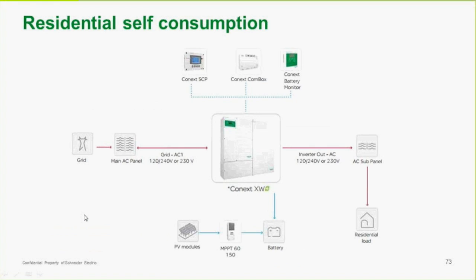Residential self-consumption. So now we're tied to the grid. We have our main panel again. But in this case, we have the PV modules and a charger, and those are actually charging the battery, and that excess power is being supplied through the inverter to the loads that are hooked up to the sub-panel. So we're using all of the power that we can get from the charging system, the PV array, and the charger.